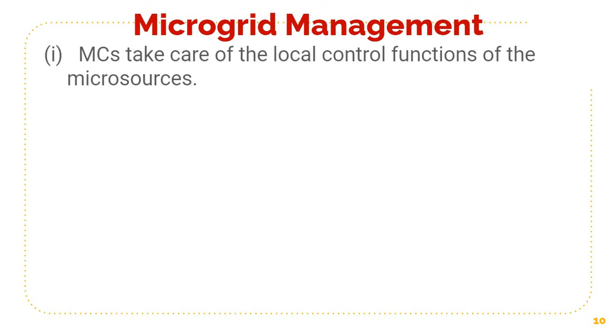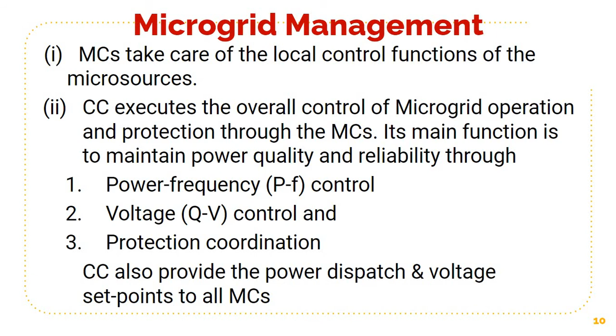The microsource controller takes care of the local control functions of the microsources, whereas the central controller executes the overall control of microgrid operation and protection through the microsource controllers. So its main function is to maintain the power quality and reliability through power frequency control, QV control or voltage control, and protection coordination. The central controller also provides the power dispatch and voltage set points to all the microsource controllers.